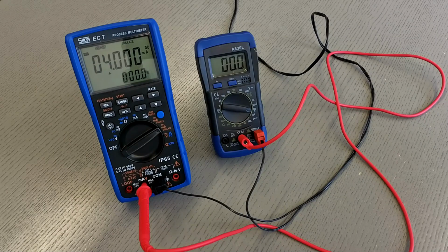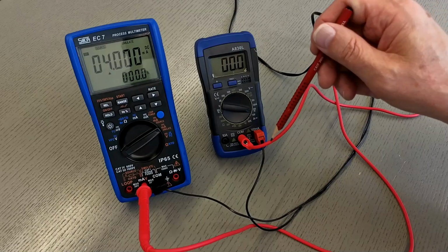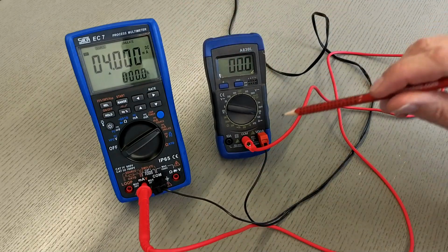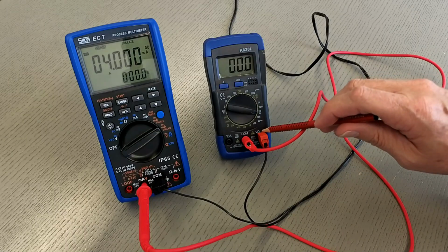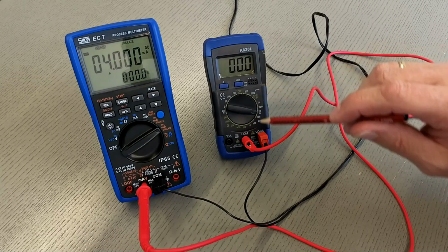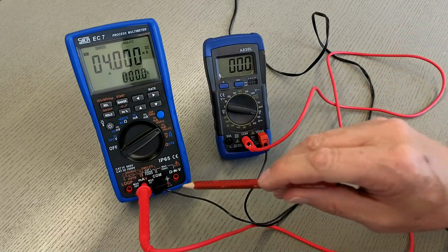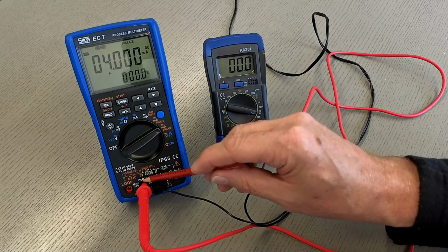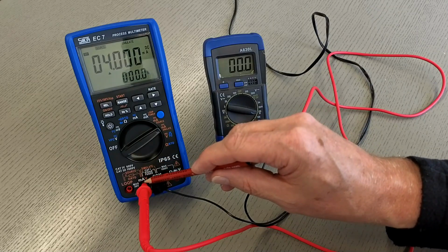That means to have a 4-20 milliamp loop, and the loop is powered by an external power supply. So I have an external power supply. The plus is here. I give the plus here to my loop, and this is my loop with an amp meter, and from the amp meter I use this terminal for the simulation of the transmitter functionality.